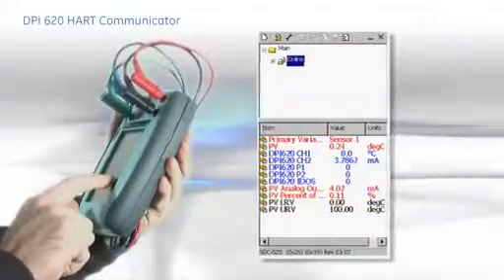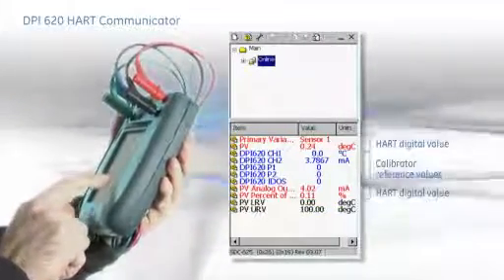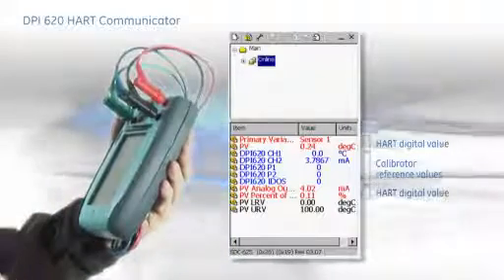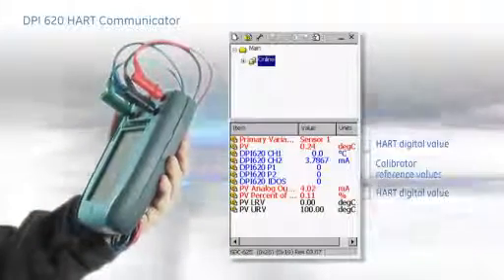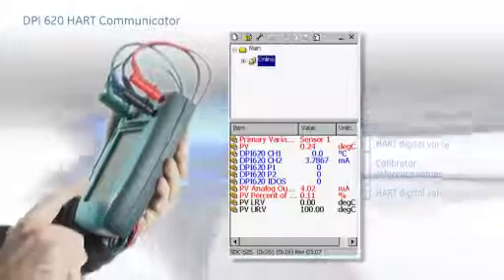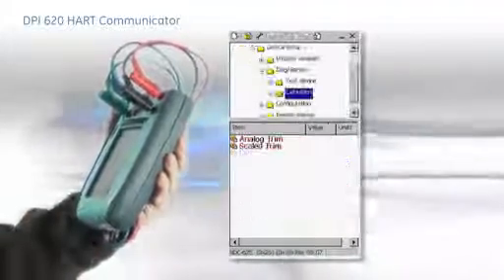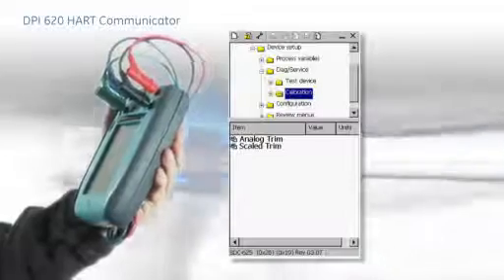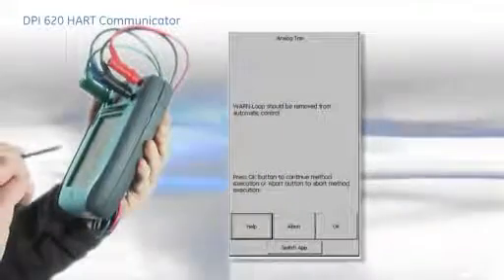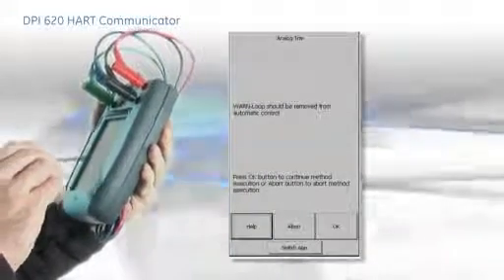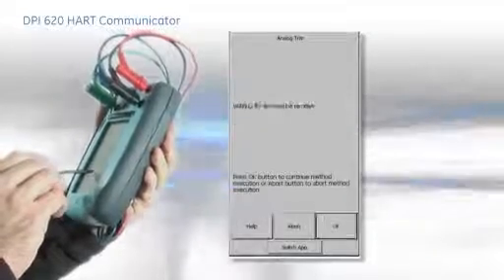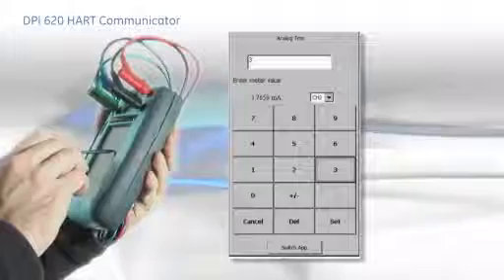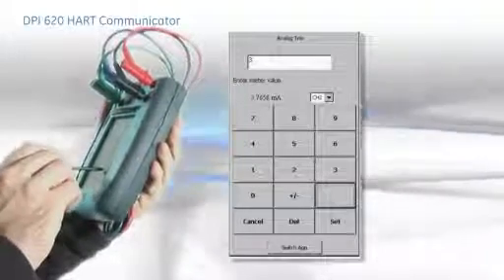Differences between the red digital values and the blue reference values indicates that a milliamp trim or sensor calibration may be required. To make a milliamp trim, simply select the appropriate method from the HART menu and follow the on-screen instructions. The DPI-620 measures the actual milliamp output of the device and the trim is performed without the need for a second instrument.